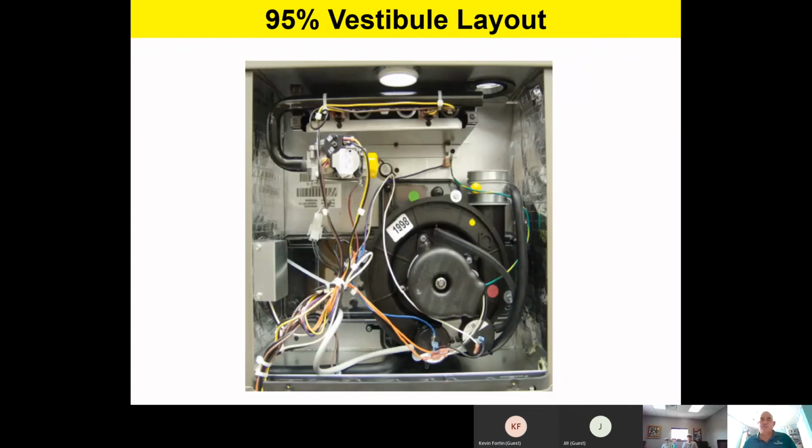Here's a 95% furnace. And when I say 95%, team, this is going to be a condensing style furnace. Any of our condensing style furnaces are going to make at least 95% efficiency. And actually, based on the furnace model that you're looking at, we go up to 98% efficiency on some of our models. So very, very efficient furnace. It's a great furnace. It's also a condensing furnace, which means that it's going to have condensate running anytime it's in the heating mode of operation as part of our high efficiency process.